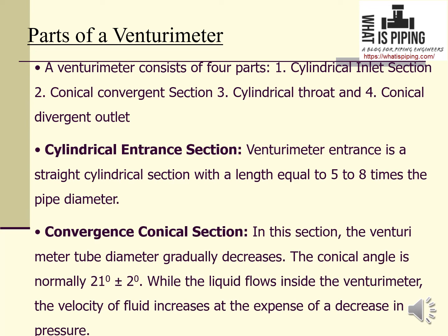A venturimeter consists of four parts: the cylindrical inlet section, the conical convergent section, the cylindrical throat, and the conical divergent outlet. The cylindrical entrance section is a straight cylindrical section with a length equal to 5 to 8 times the pipe diameter.